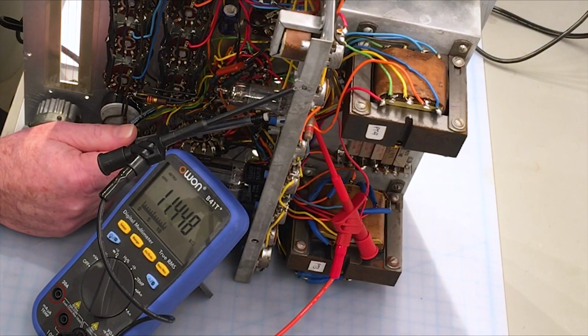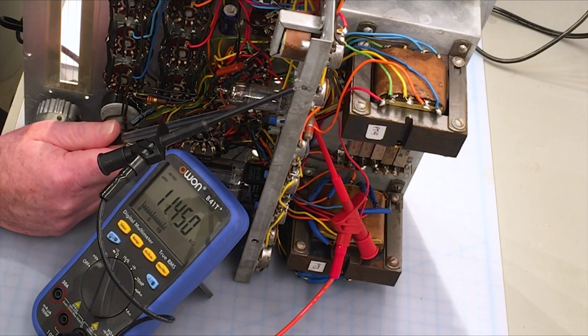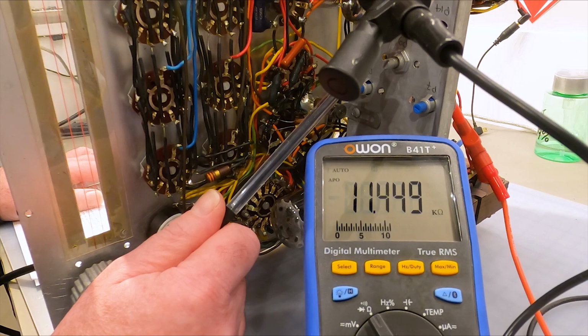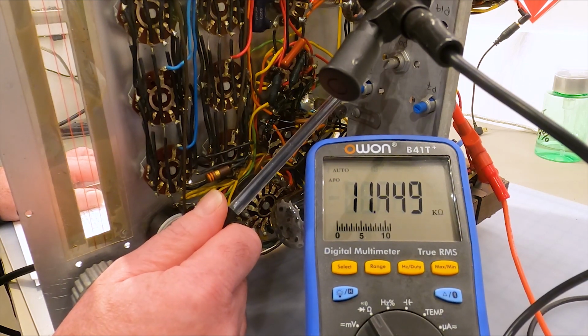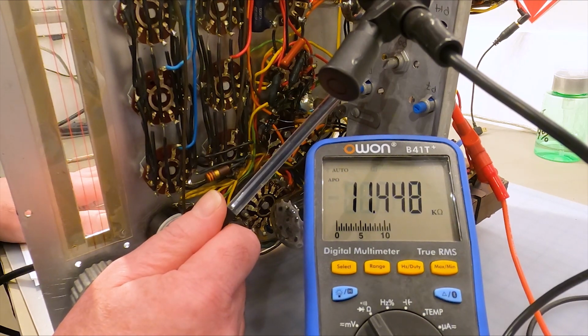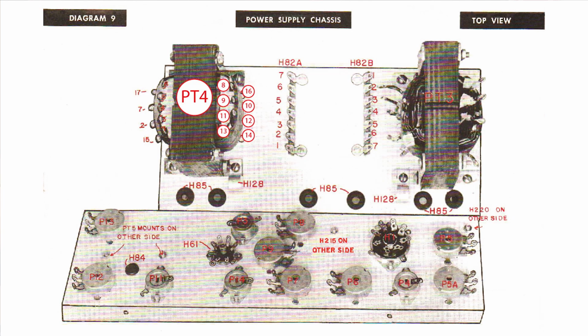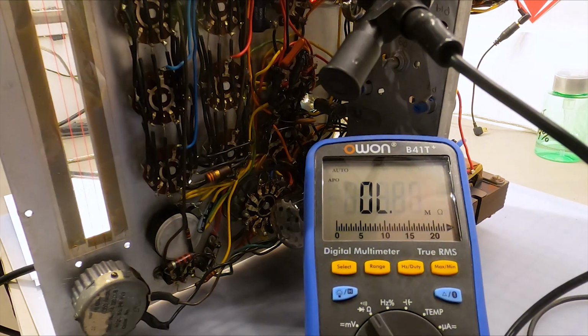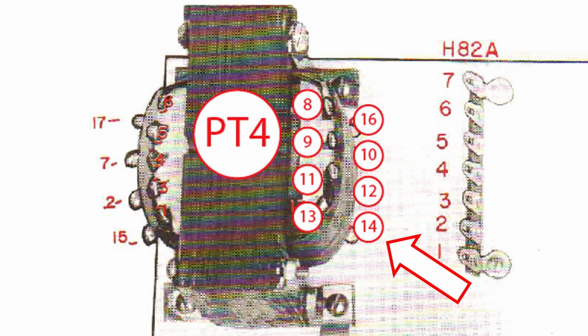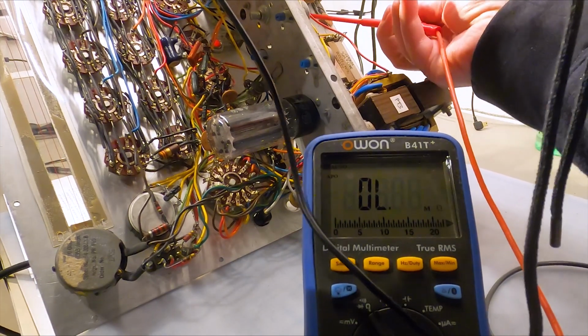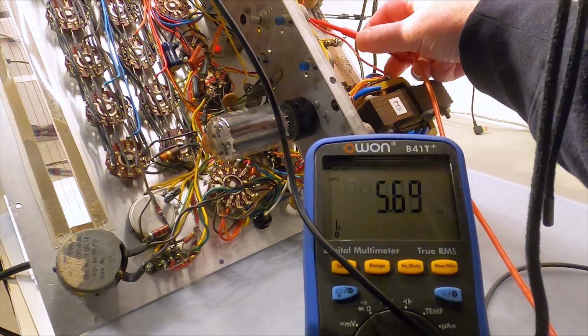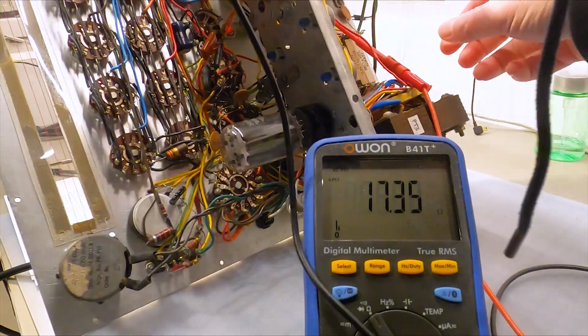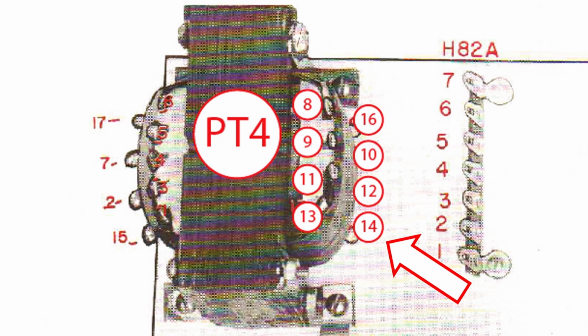Again, we have not adjusted the trimmer potentiometers to their full travel, so this value may be off slightly, but it's greater than 8K, and that's fine. So now we're to connect an AC voltmeter from ground to terminal 14 of power transformer 4, and we'll do that. Lead 14 is the one that is closest to the center, and I'm going to have to tip the tester forward here. So it's the one closest to the center on the bottom of power transformer 4.